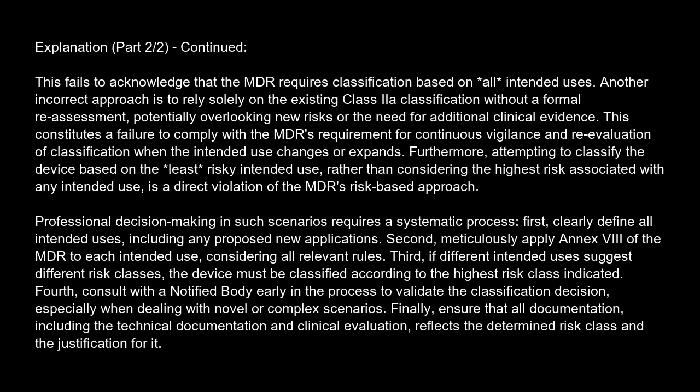This constitutes a failure to comply with the MDR's requirement for continuous vigilance and reevaluation of classification when the intended use changes or expands. Furthermore, attempting to classify the device based on the least risky intended use, rather than considering the highest risk associated with any intended use, is a direct violation of the MDR's risk-based approach. Professional decision-making in such scenarios requires a systematic process. First, clearly define all intended uses, including any proposed new applications.